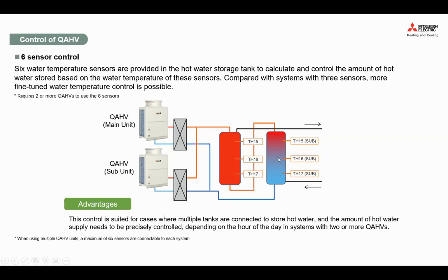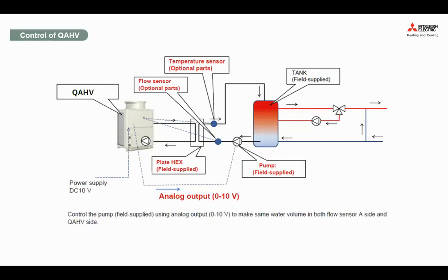However, during the nighttime, you want to fill the tank as much as you can because you want to offset your load during the nighttime. So you fill the water, and the unit will be on and off depending on your sub thermistor and temperature sensor. So here is just another example. The QAHV can also take 0 to 10 volt and send a signal out to control your external pump, depending on what's required. And depending on what's required, you can also recirculate your water temperature on the other side. So you can have field supply, analog output, input, just to make sure there's no dry run in the system.